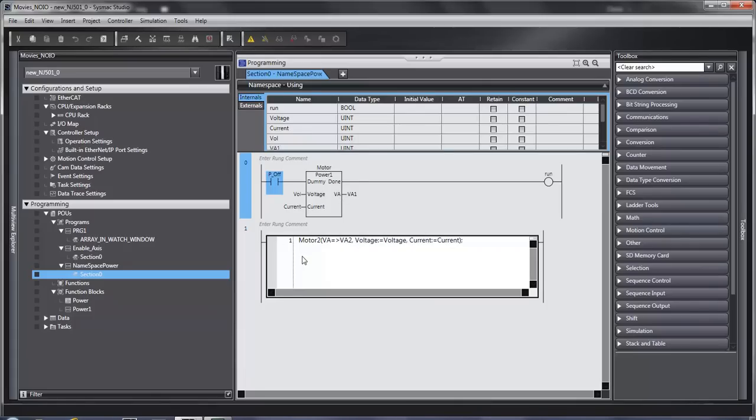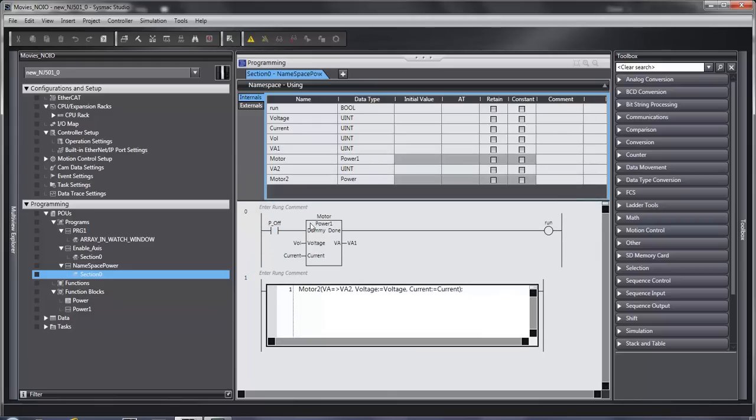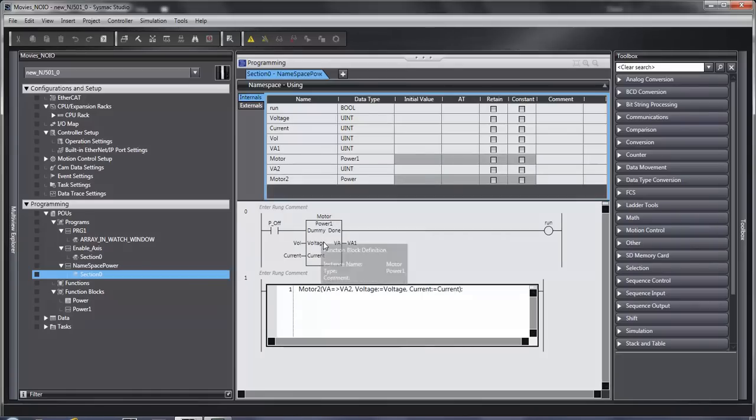If you were going to use the function block in structured text, a couple of things you need to know. First of all, you have to declare. Unlike in ladder where you call it by its name, in structured text, you call it by its variable name.